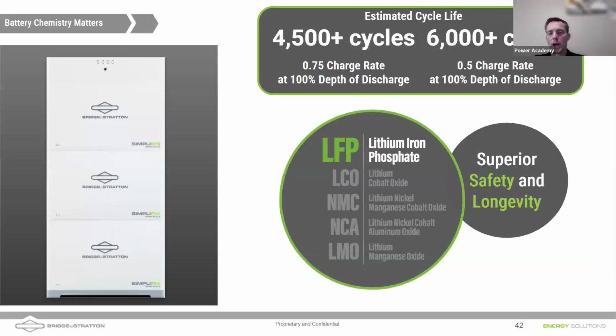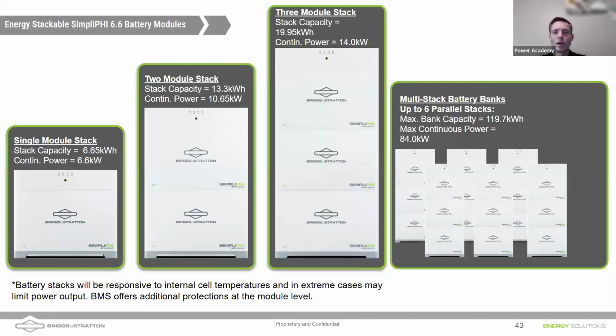I do want to highlight this battery that we've got. So this is our newer battery, 6,000 cycles at a 0.5 C rate, 100% depth of discharge, outdoor rated battery. If you haven't installed one yet, they're remarkably easy to put in. Indoor, outdoor, you can do up to 6 of these stacks.